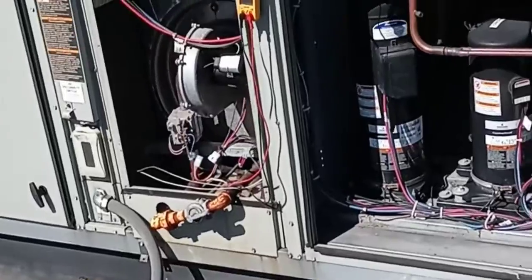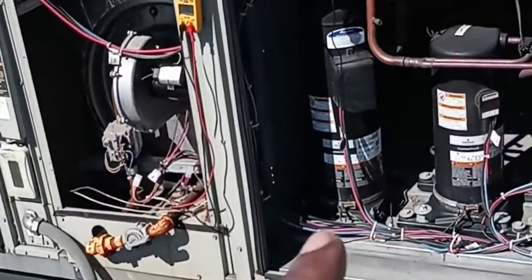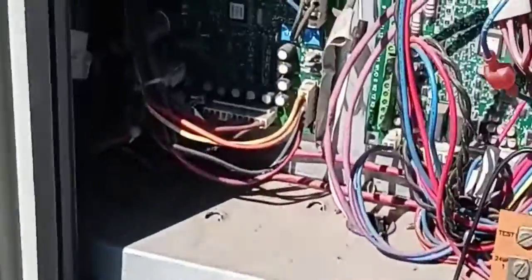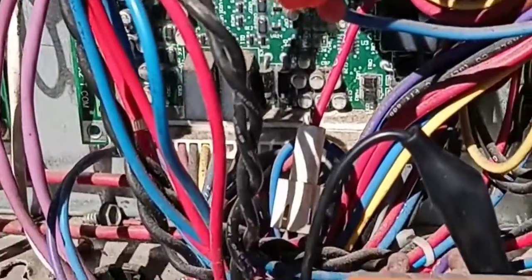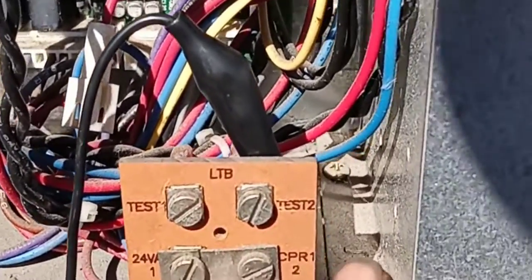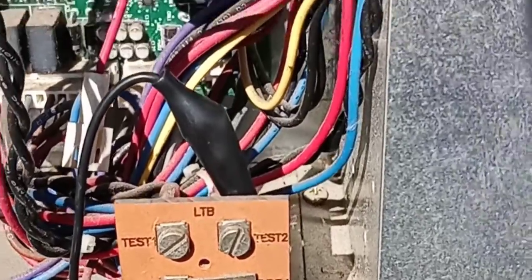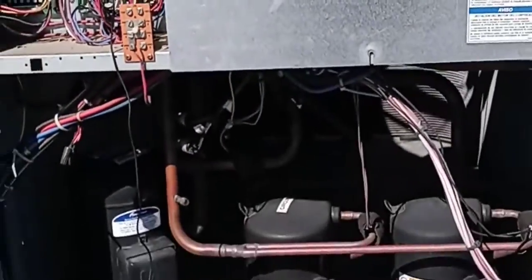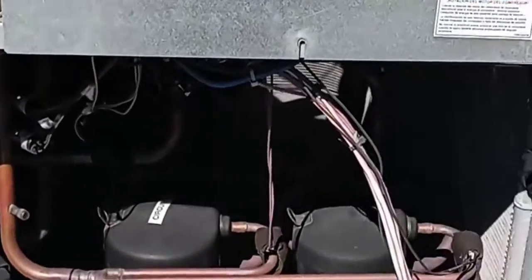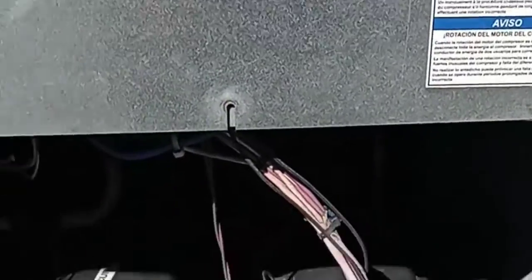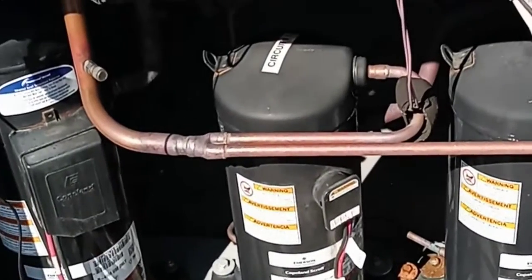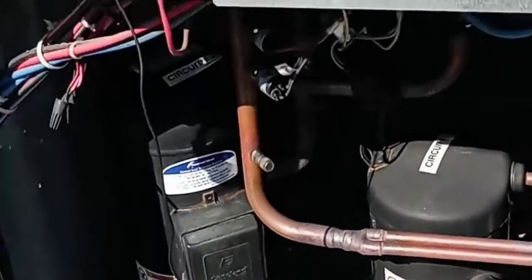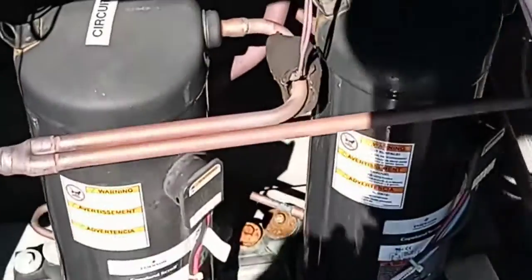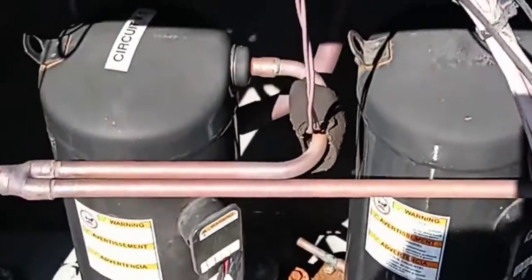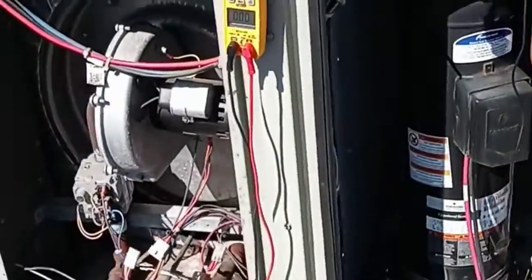So if I leave a jumper on test 1 and test 2, it'll cycle through all the modes. It'll stay on fan for 5 minutes, then it'll jump into air conditioning, it'll turn on the first circuit for 5 minutes, then it'll turn on the second circuit, 5 minutes. These are tandem compressors too, by the way. I love those things. So when I did my test mode, air conditioning ran fine, fan ran fine.